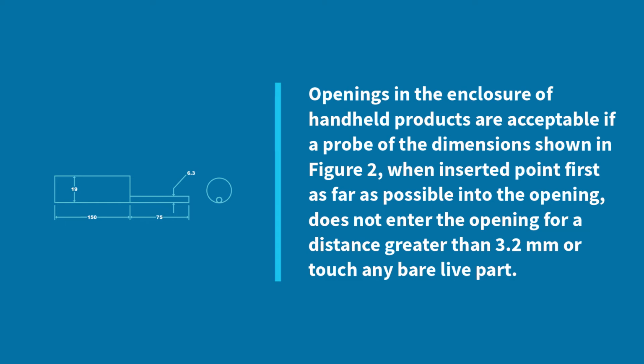Openings in the enclosure of handheld products are acceptable if a probe of the dimensions shown in Figure 2, when inserted point first as far as possible into the opening, does not enter the opening for a distance greater than 3.2 millimeters or touch any bare live part.